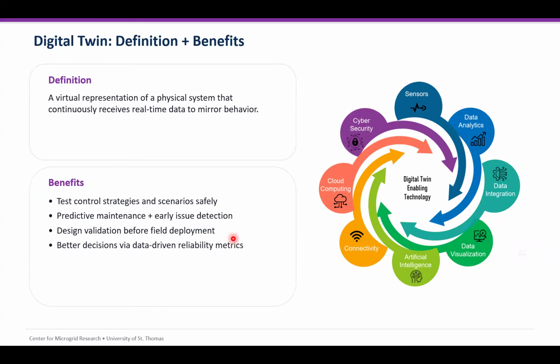Another development in the area of the microgrid is what's called the digital twin. A digital twin is basically a virtual representation of a physical system that continuously receives real-time data to mirror behavior. So we use the digital twin in the center to test microgrid behavior or performance in case we are introducing a new controller or adding new equipment. Instead of doing that in real life, we do it on a digital twin. And this digital twin showed very close matching with the real world results.